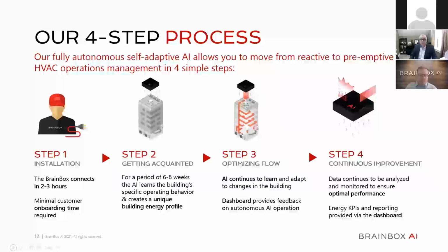So first, I want to go over the process of how BrainBox deploys and implements, and we call it a 4-step process. I'll go through each one. The first stage is to get connection from the cloud to the BAS. We have 2 ways of doing that. We install an edge device on site that's connected to the BAS network, or we install a software driver if it's a Tridium Niagara installation. Between the two, it's 2 to 3 hours, 3 hours being on the long side, typically under 2 hours to install.